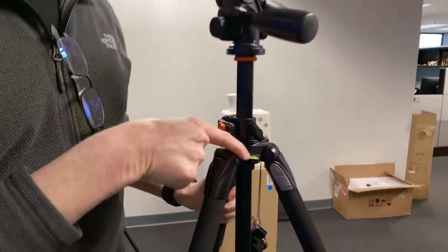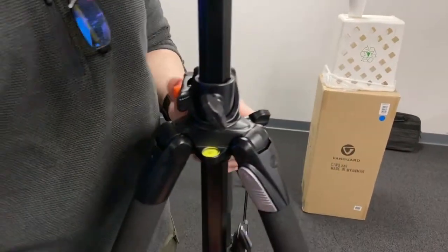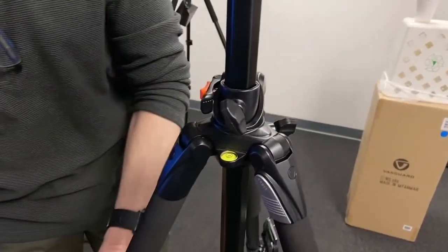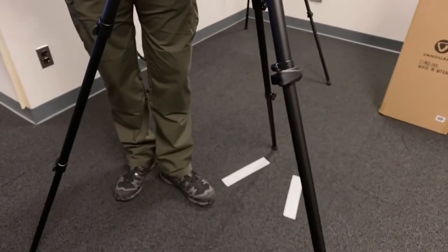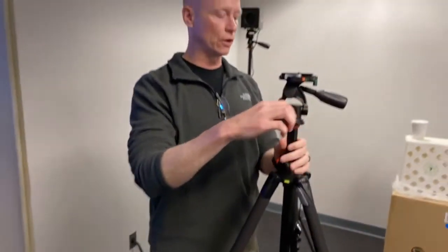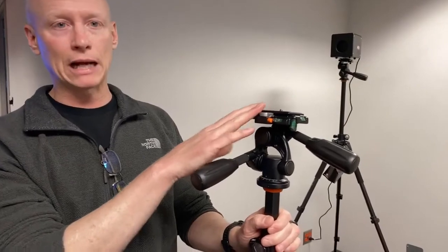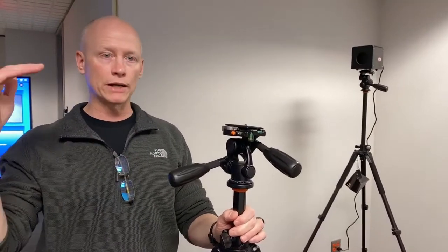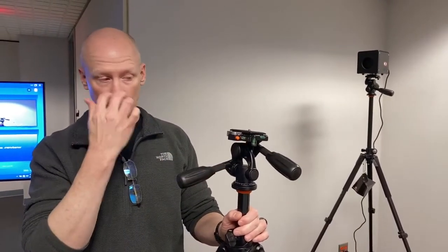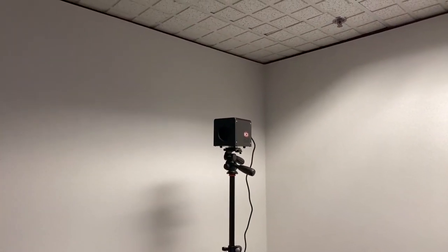The level: you'll notice right here that there's a bubble level on the tripod base. So make sure that your tripod is fully locked out on the detent on these legs. Make sure your friction locks are actually set, nice and secure, fully extended, so the tripod base is very stable and level. We already went over the spikes and the rubber feet on the bottom, but the other thing to note here is that on the tripod head, you have a variety of bubble vials. The camera and the black body do not need to be perfectly level. Set up the camera as we have done in our setup, where the camera height has a slightly downward angle tilt to get a good visual on the tear duct area. For the black body, you want to make sure that this circular opening faces the face of the camera and it has a good line of sight. That gives you the best alignment.